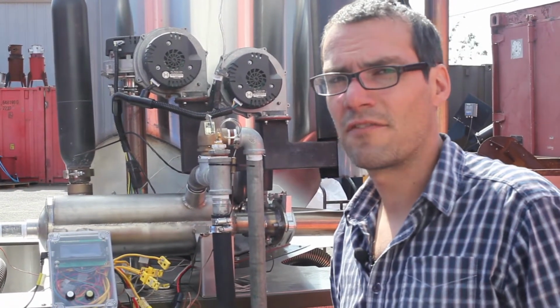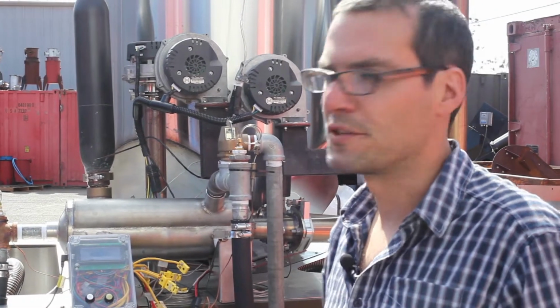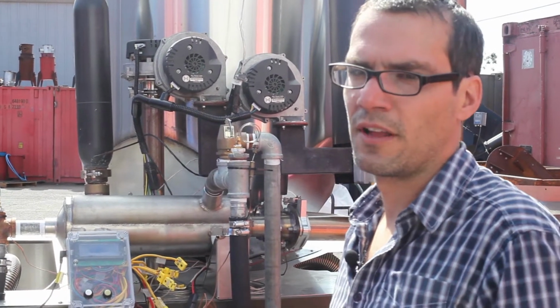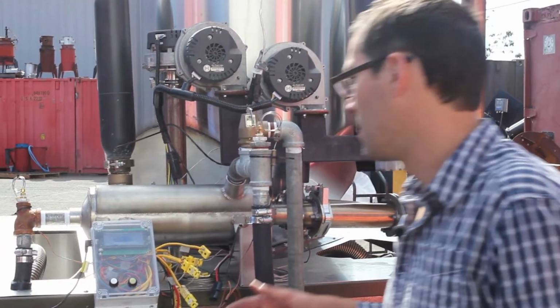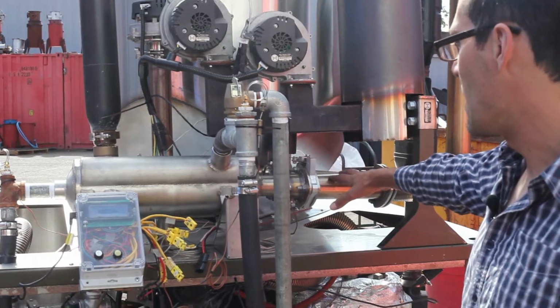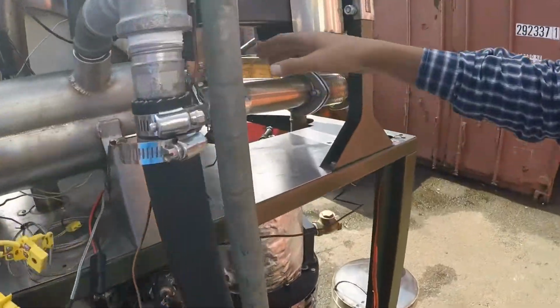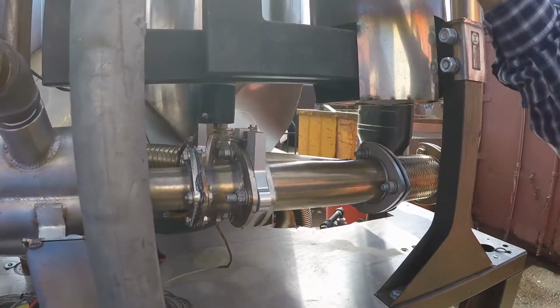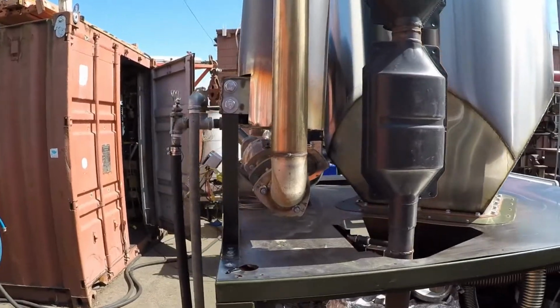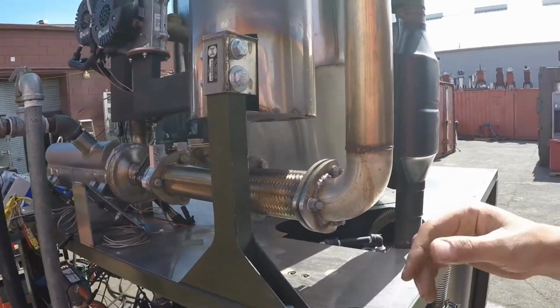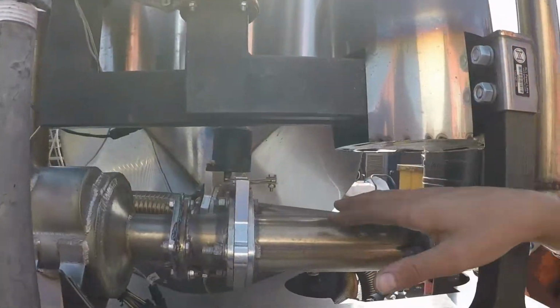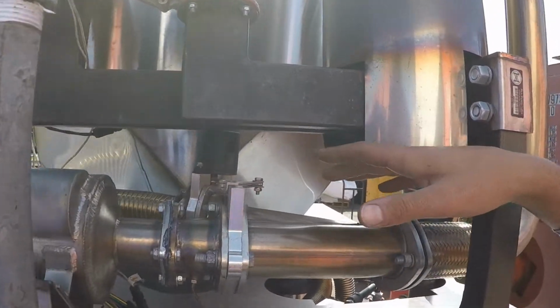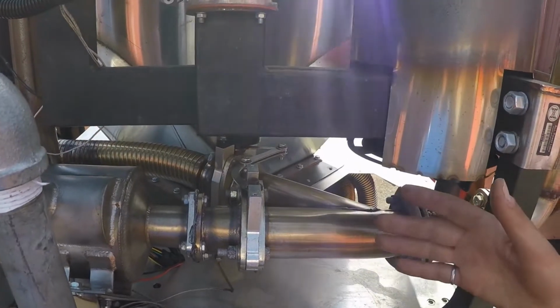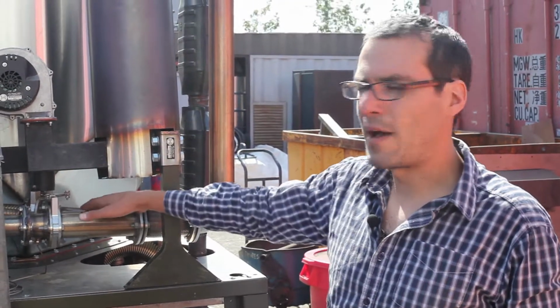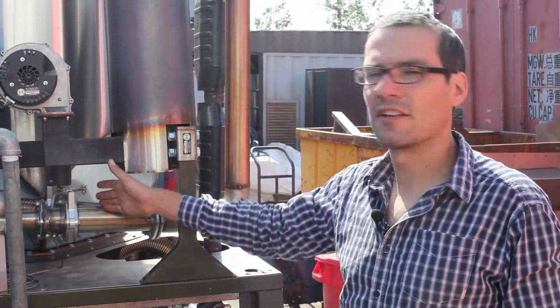If we have high return temperatures to the CHP system, because there's not enough heat being dumped where the hot water is being used, say in a warehouse or in crop drying or something, then we have an exhaust gas bypass valve. So we bypass the shell and tube heat exchanger and send the exhaust gas straight out. And this allows us to safely operate the system with high return temperatures in the working loop, or if the customers want to use the power cube without the combined heat and power system, then we use this bypass valve to direct the exhaust gas past the heat exchanger rather than through it.